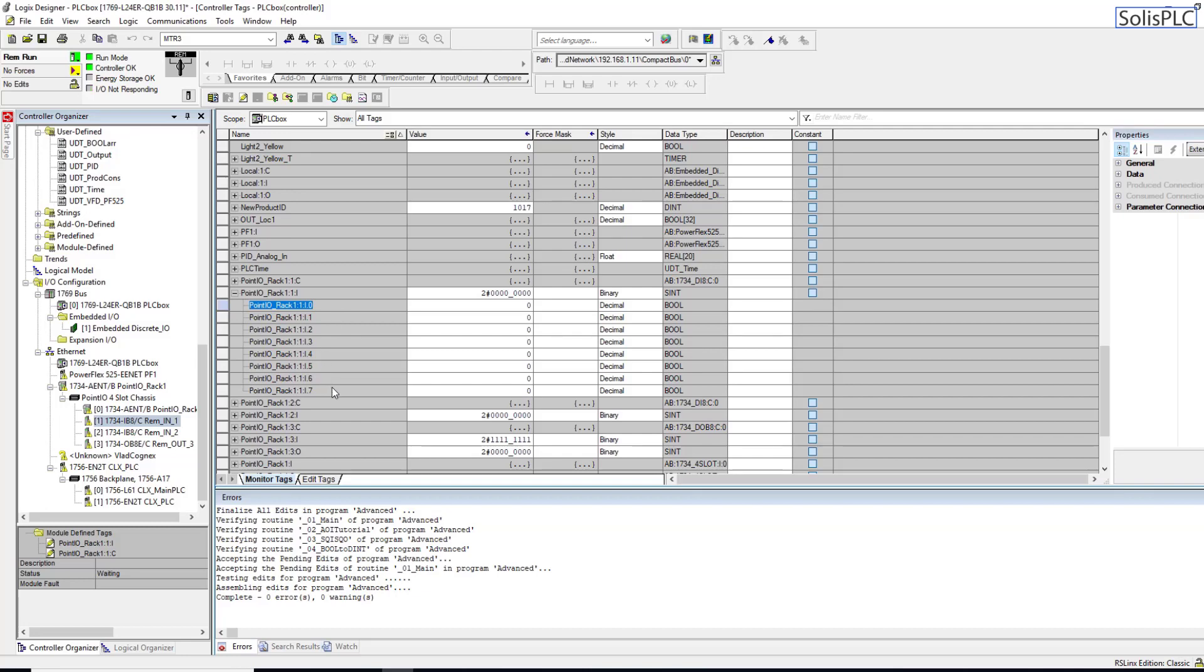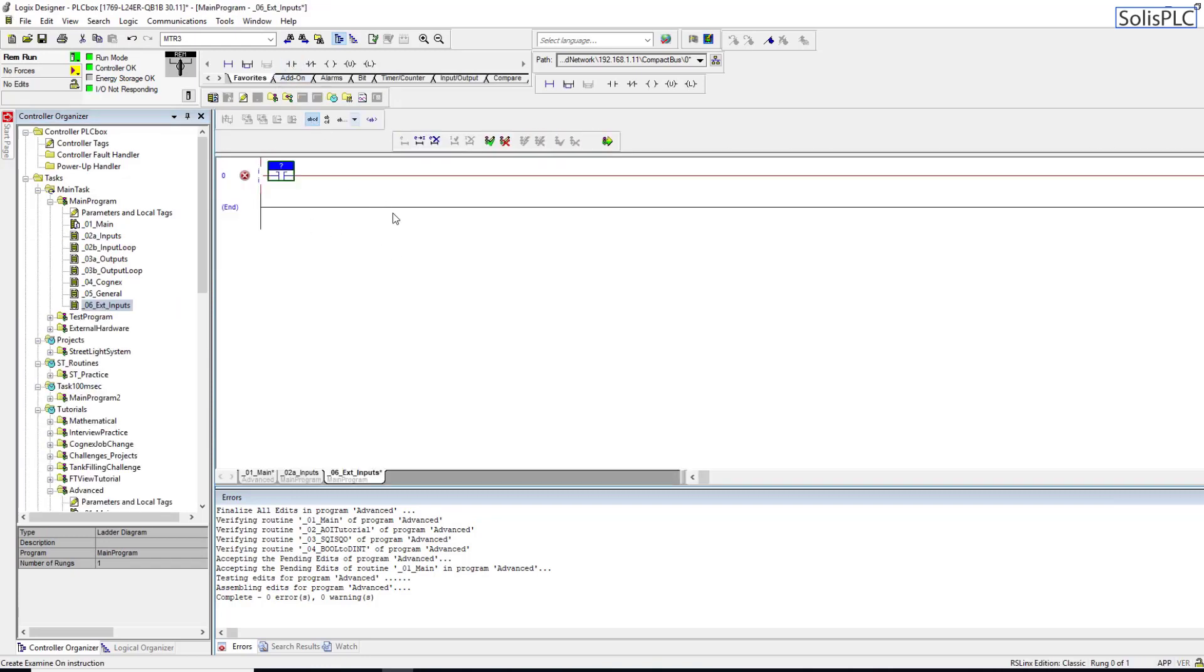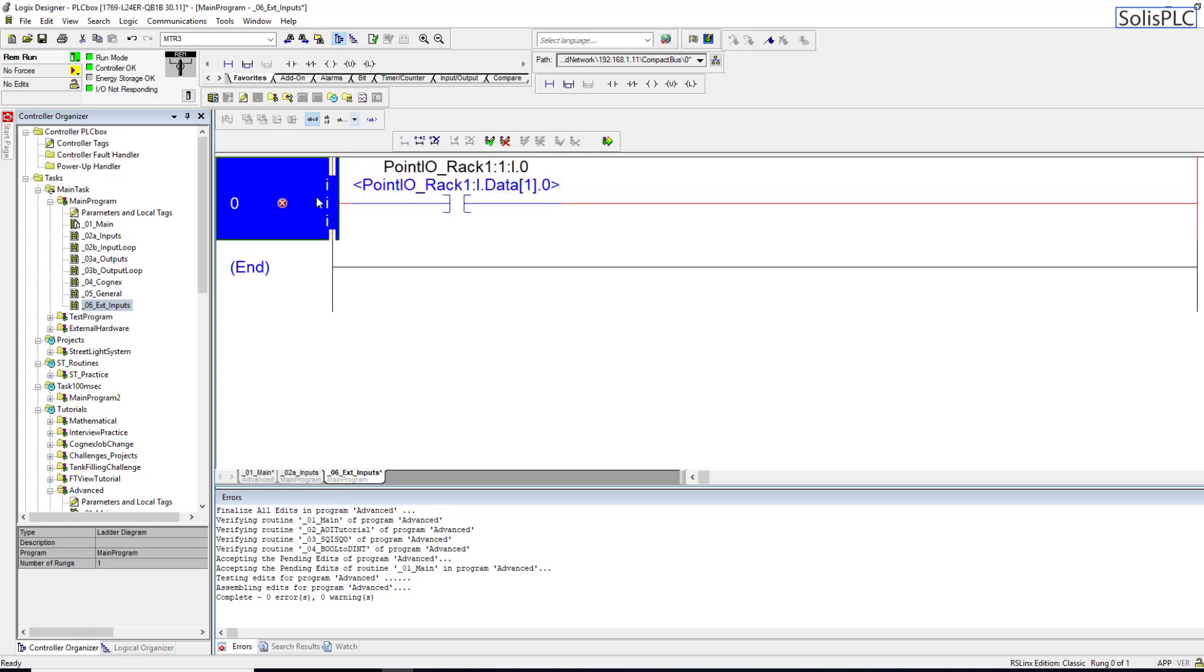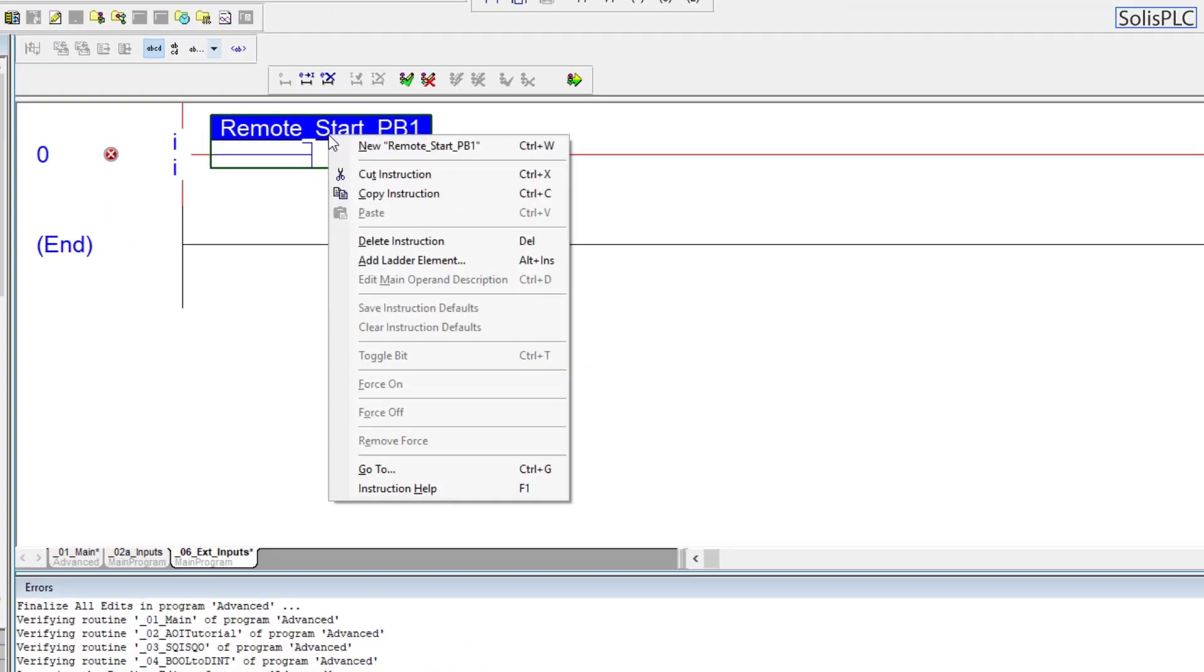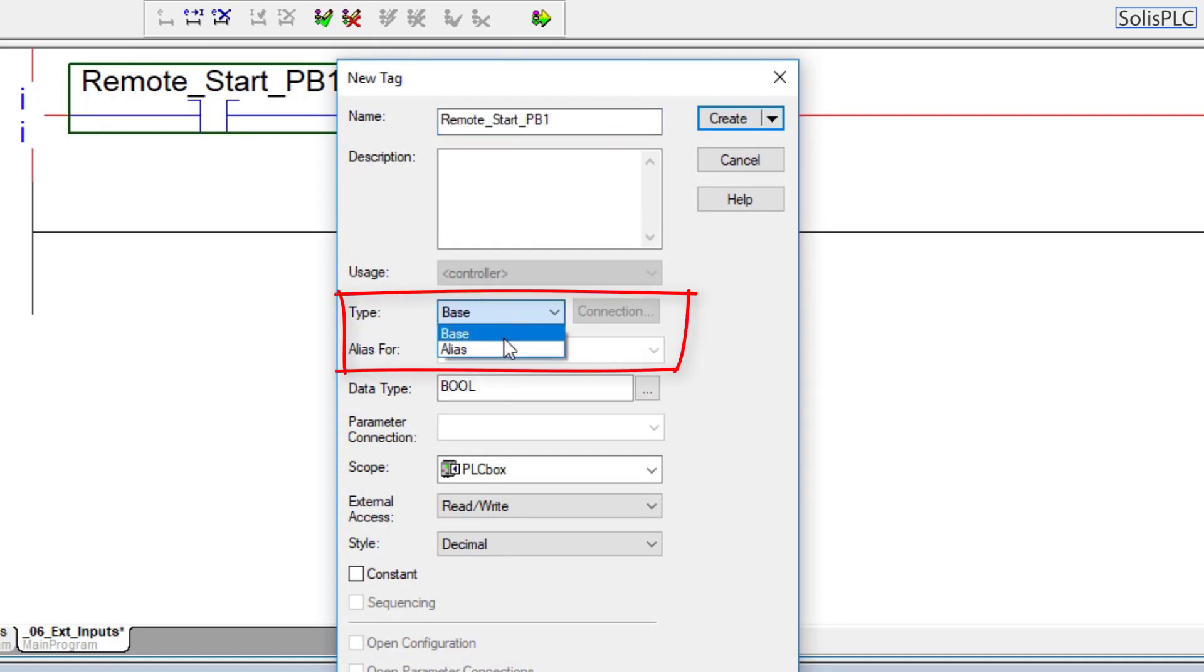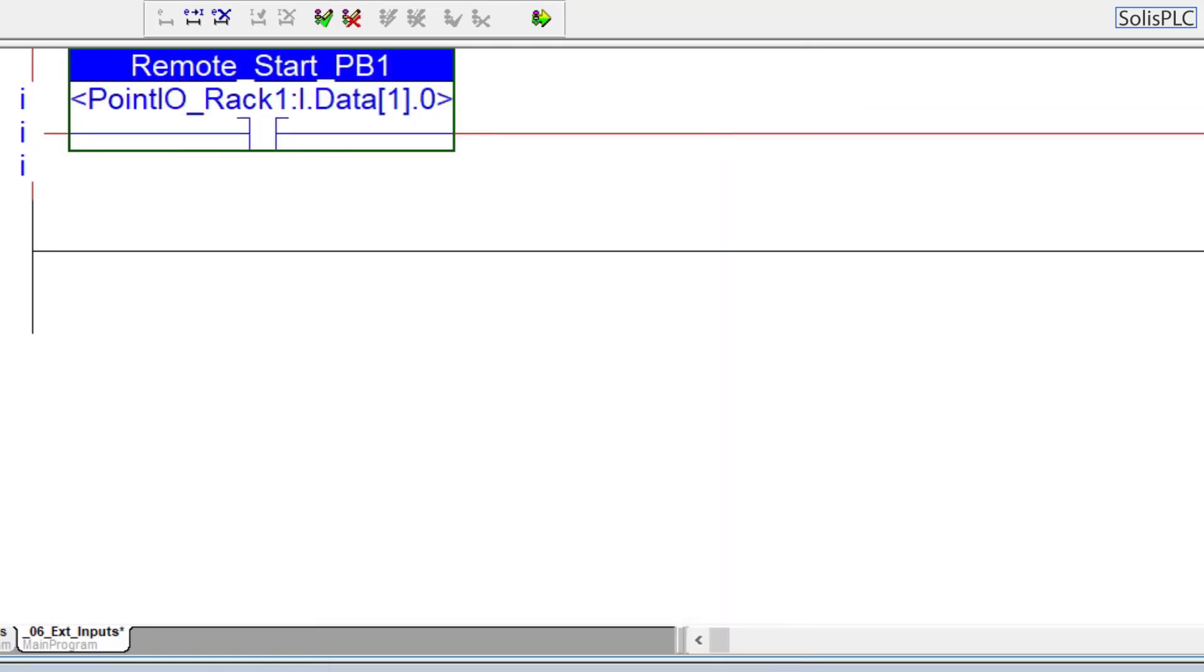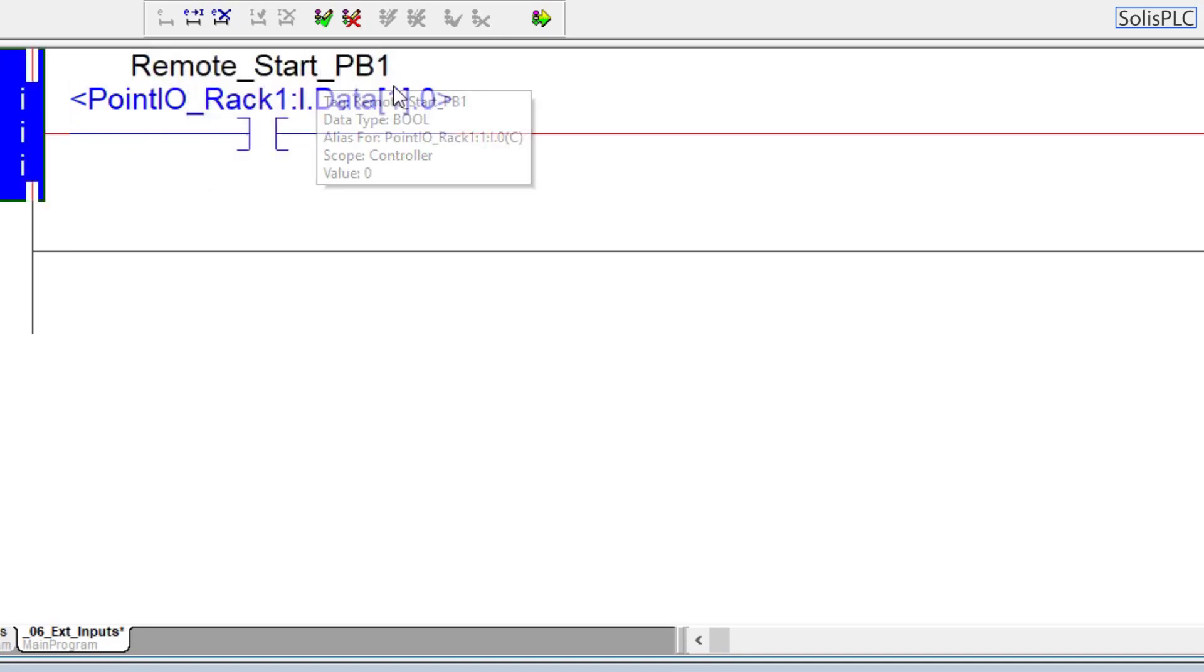I'm going to copy this and go back into the program External_Inputs. Instead of typing in this long name you can type in something like Remote_Start_PB1 - this is a remote push button which is going to be start. I'm going to right click this and create a new start push button. Instead of setting this tag type to base I'm going to select alias, and for alias I'm going to type in the tag which was brought in by the Point IO and hit create.